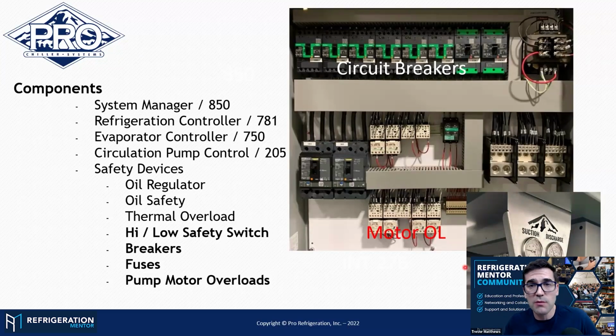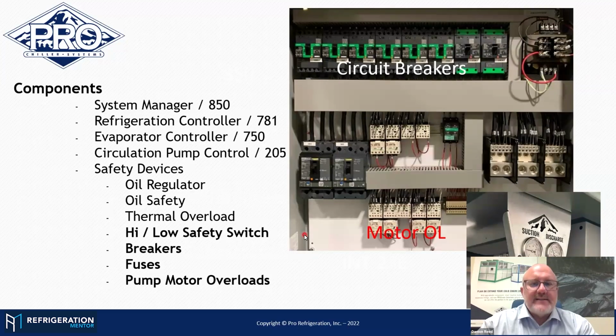If you see something trip, like we talked about before, the Delta P for example, you don't just go and reset it without thinking, what am I going to do? My gauge is already hooked up to check the pressure differential, things like that. So I love those points, Damon. Yeah, so that's just kind of in summary with the controls before we jump into the order of operations.